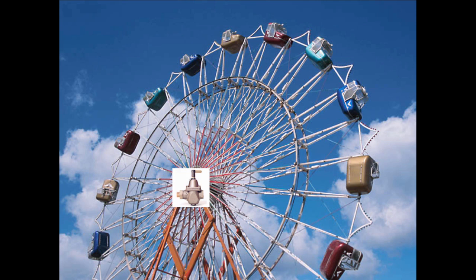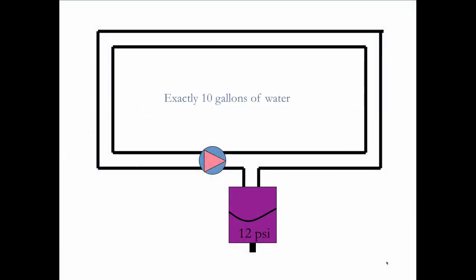When we talk about pump head, we're not talking about the height. Like a Ferris wheel, the weight of the car going up here is balanced by the weight of the car coming down. In a hot water heating system, we use a fill valve to fill the system completely to the top and put it under a few pounds of pressure. So there's no lifting involved. When a circulator comes on, it's very much like the motor on a Ferris wheel in that it's not doing any lifting at all. It's just turning this big wheel of water. So when we say pump head, we're not talking about height. We're not talking about the size of the building.